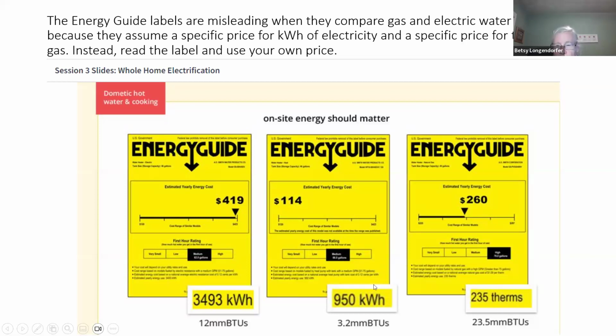This was put in larger type. In order to do the real comparison, you have to convert to BTUs. This is a regular standard storage tank electric heater that uses about 12 million BTUs a year. This is a heat pump water heater — it uses 3.2 million, about a quarter of the BTUs. And this is a gas water heater that uses almost 24 million BTUs, about twice what the electric water heater uses. Gas versus electric doesn't compare well on the stickers, so don't look at the stickers so much — look at how much energy it's actually using and what the cost of that energy is.